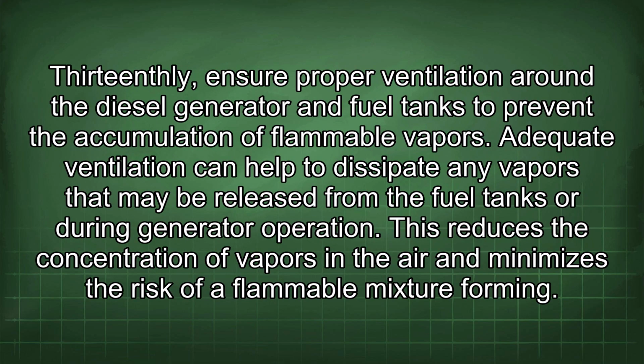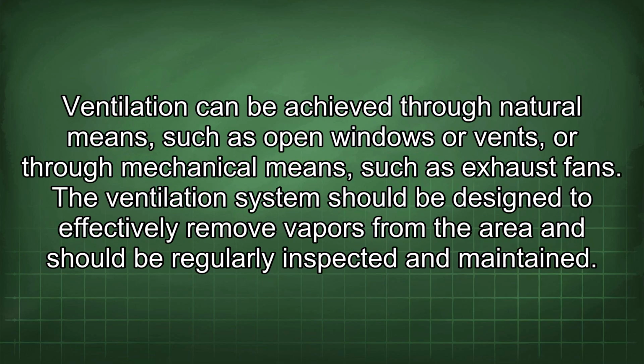It's important to consider all potential sources of flammable materials when assessing the hazardous location classification and designing the electrical system. 13thly, ensure proper ventilation around the diesel generator and fuel tanks to prevent the accumulation of flammable vapors. Adequate ventilation can help to dissipate any vapors that may be released from the fuel tanks or during generator operation. This reduces the concentration of vapors in the air and minimizes the risk of a flammable mixture forming. Ventilation can be achieved through natural means, such as open windows or vents, or through mechanical means, such as exhaust fans.